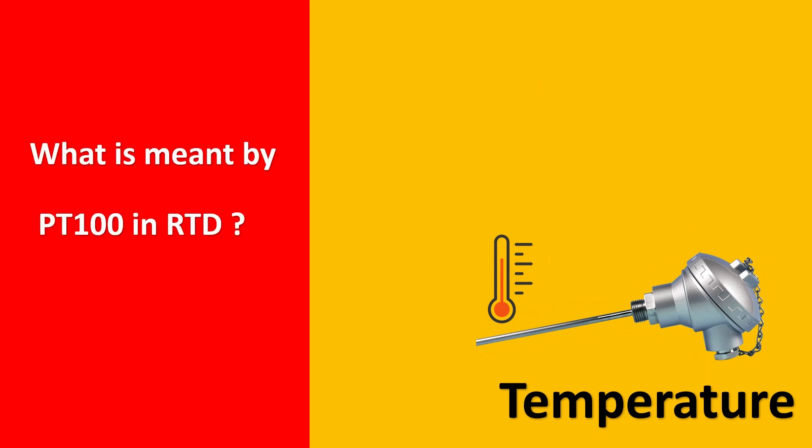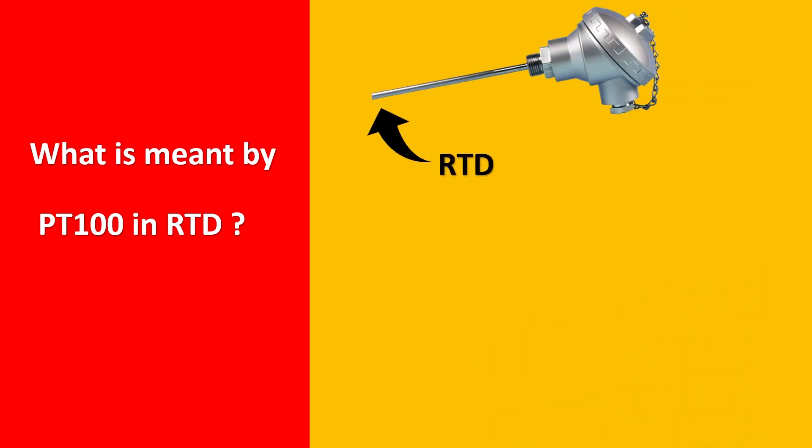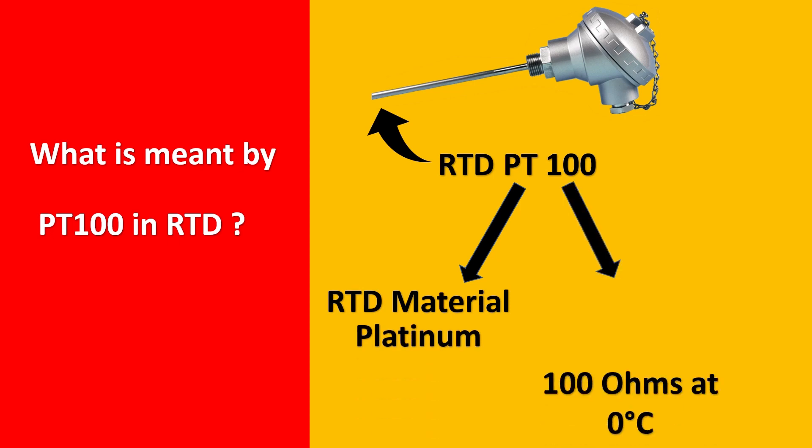But it has been asked a lot of times that is what is PT-100 in RTD? So in RTD, PT-100 is basically the PT stands for the material which is platinum and the 100 stands for 100 ohms at 0 degree Celsius.